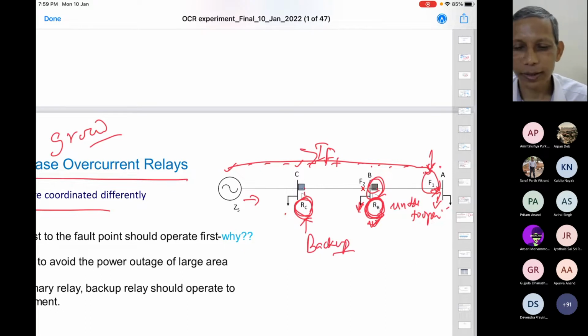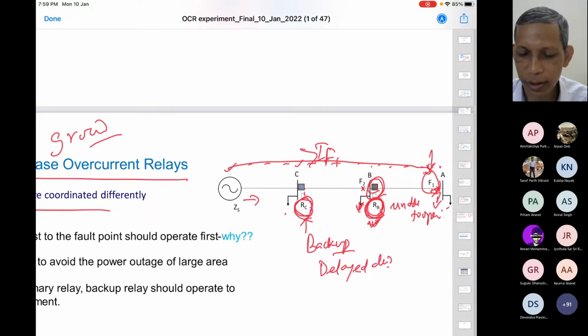The RC acts as a backup. You understand what is RC backup? So what will happen is that the RC here waits for some time, a delayed decision. It waits for some time and watches, and then says that no, there is a problem with something, and then it opens here. Is it not good? It is good for the system. So this is called a backup protection arrangement. But then RC should never operate before the operation of RB.